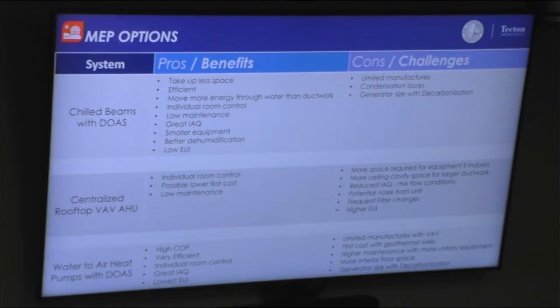What's a con? There are limited manufacturers on the market that do this. It's not like I have 20 manufacturers I can go to. There's 3 or 4 that we can use, but it's a smaller pool. Condensation could be an issue, but to mitigate that, we make sure we control our dew points within the building, and we can provide drain pans in the chill beams, so we don't have to worry about condensation issues. So that's not going to be a concern. I mentioned generator size because if we go chill beams with DOAS and all electric, we'll have that. If we don't, with the fossil fuels, smaller, it'll still be fine. But then that'd be actually a plus.